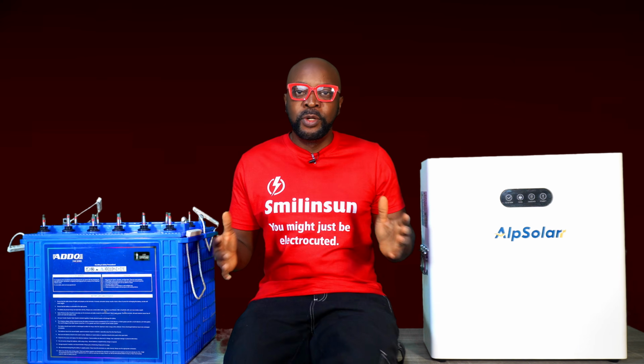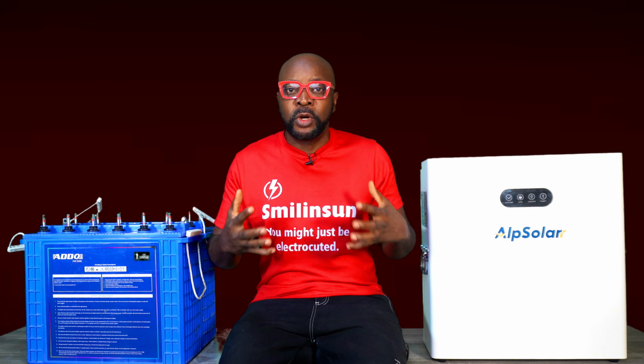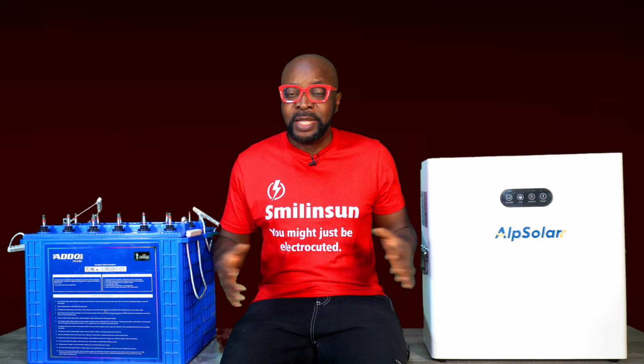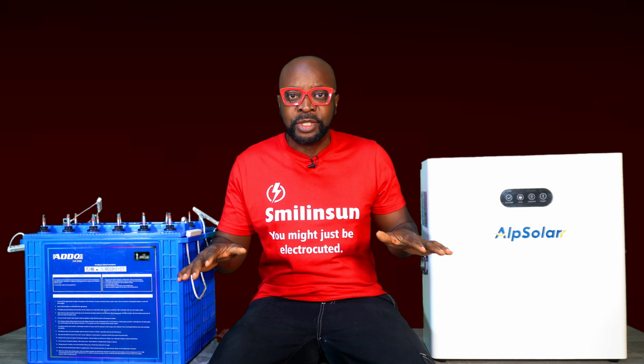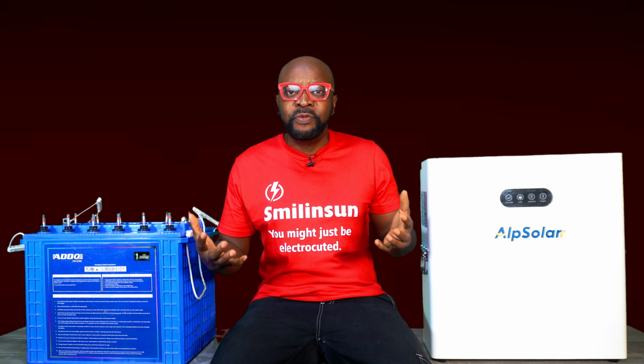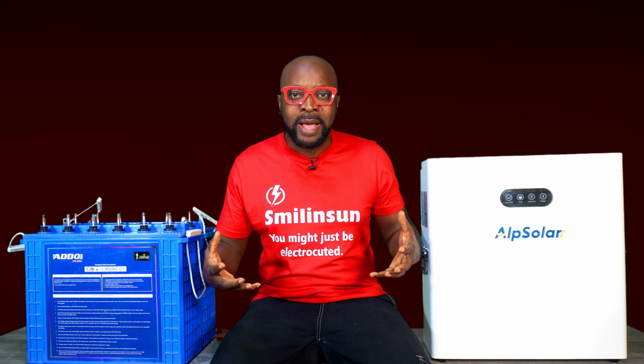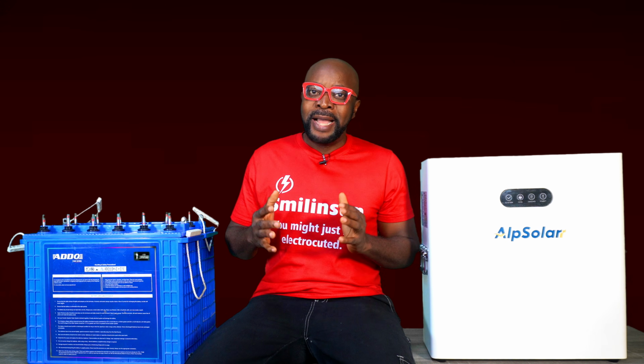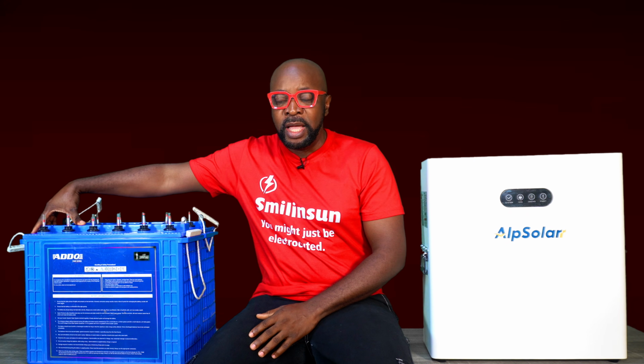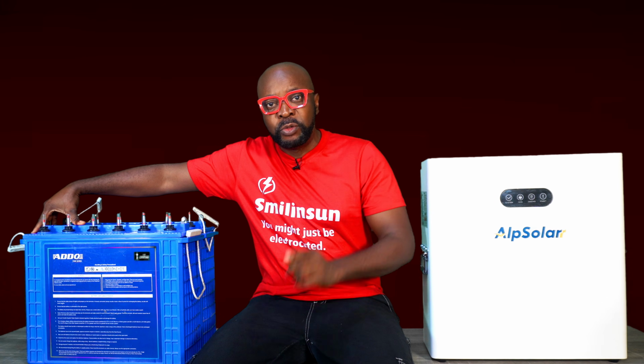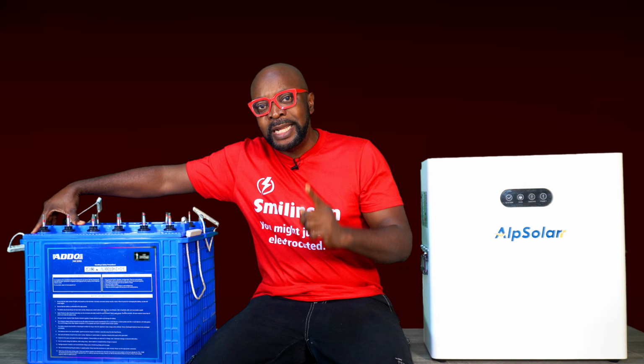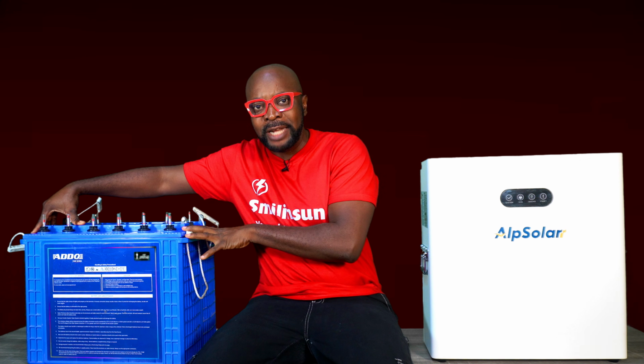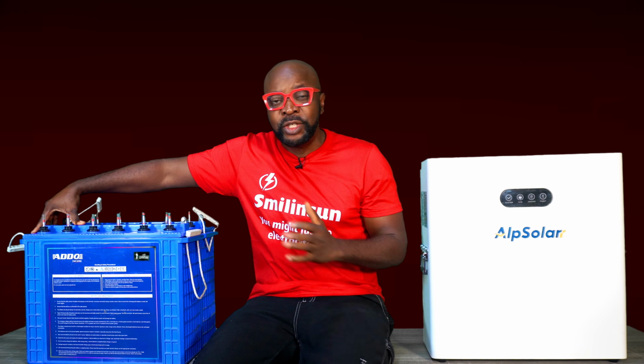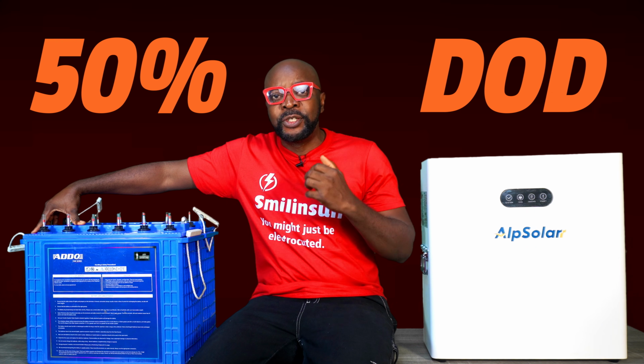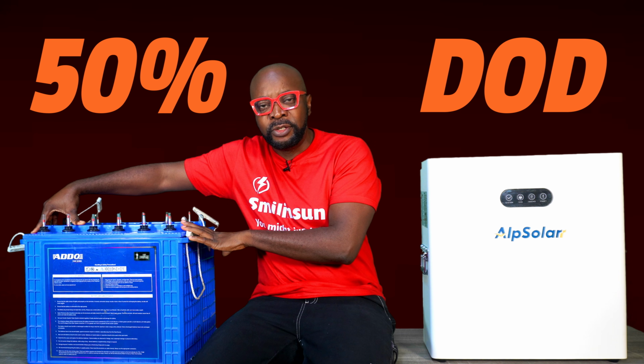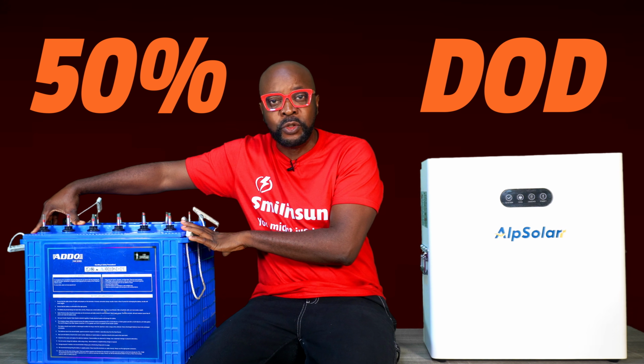All right, let's look at the energy density, the energy storage capacity of both batteries. Now, when you have the batteries fully charged, the question is, how much energy can you extract from these batteries? Let's look at the tubular battery, which is a flooded lead-acid battery. The manufacturers recommend a 50% energy extraction. So what they're saying is that when the battery is fully charged, you can only extract 50%. That's the recommended threshold. You should never push beyond that limit.